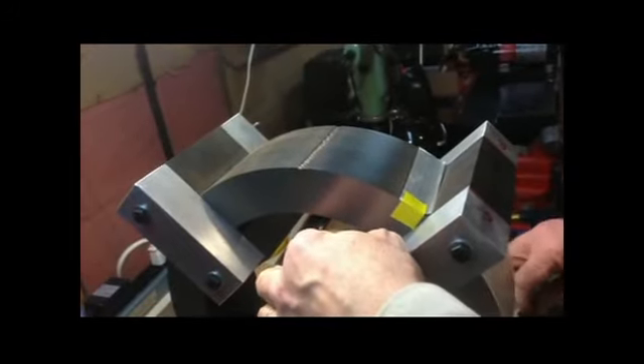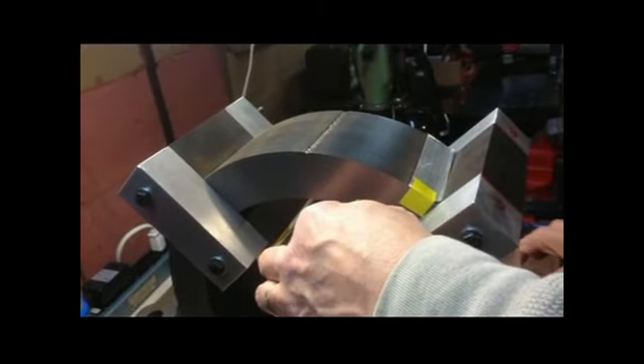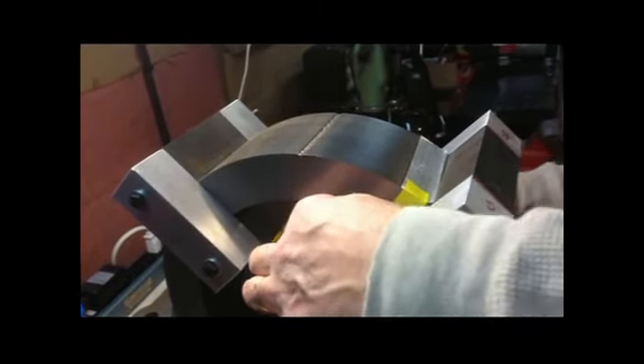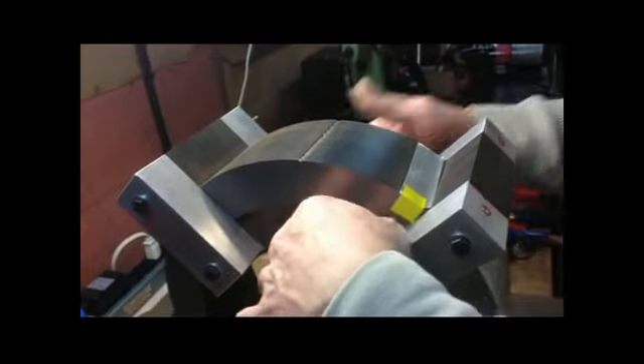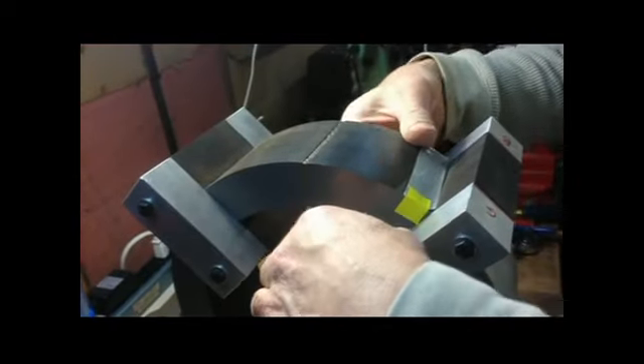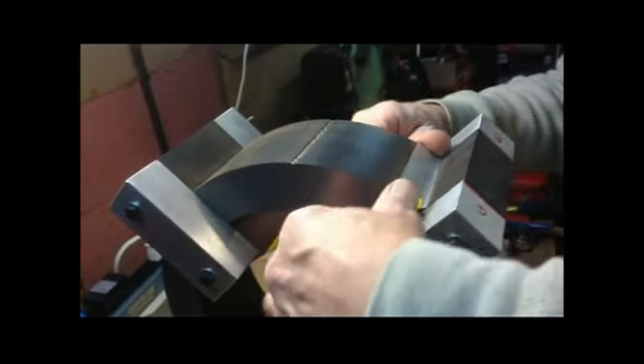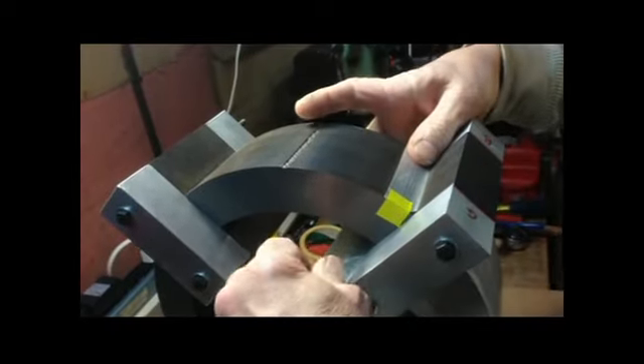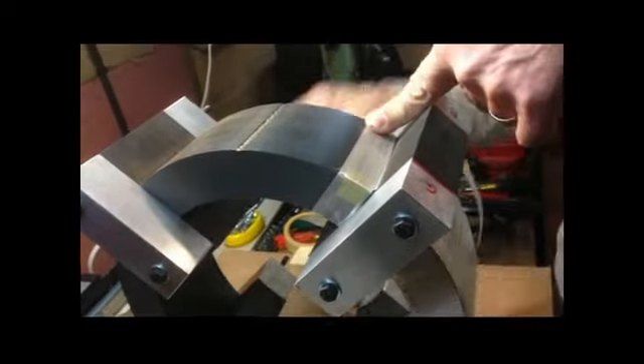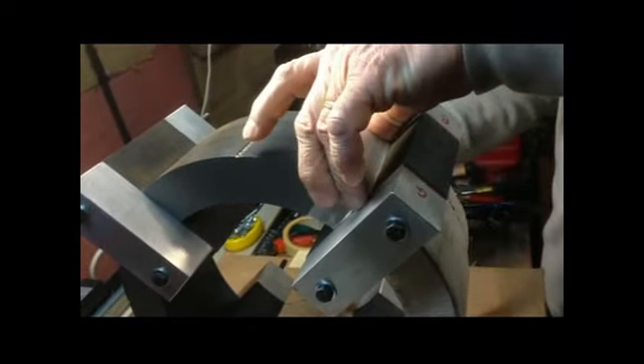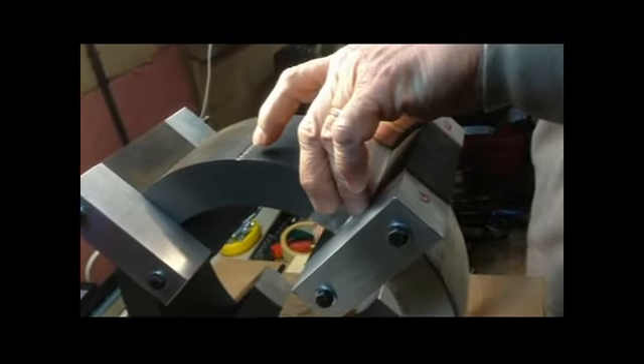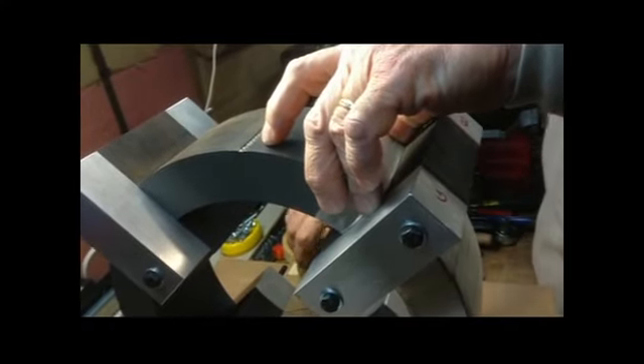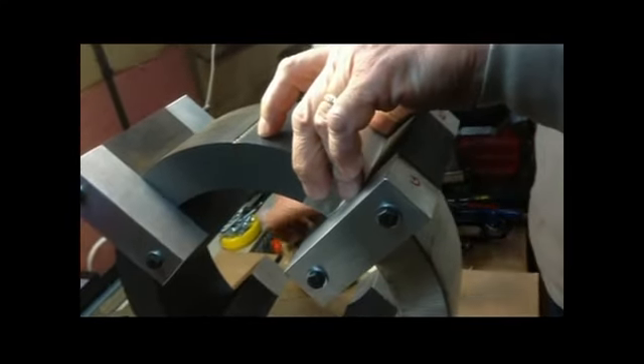This is mica tape. It's impregnated with mica, so it has high voltage insulating qualities. This is called ground wall insulation—ground like earth. This is your primary insulation between the copper and the steel core.